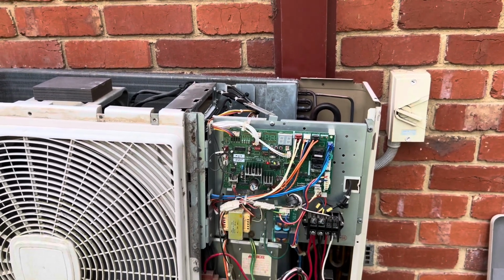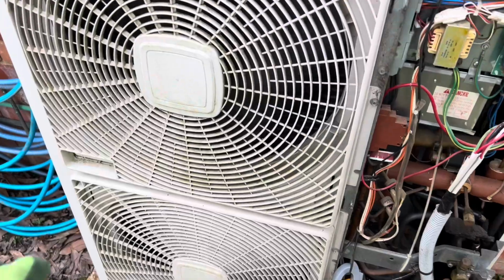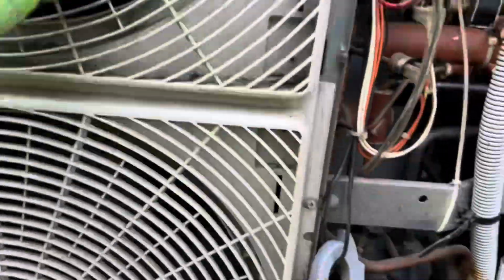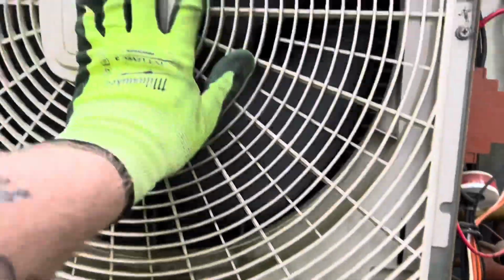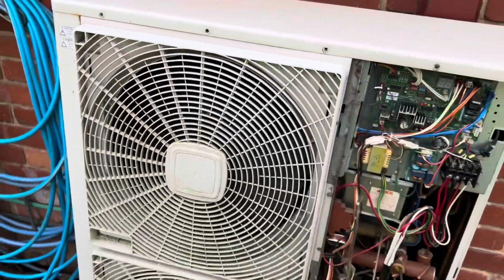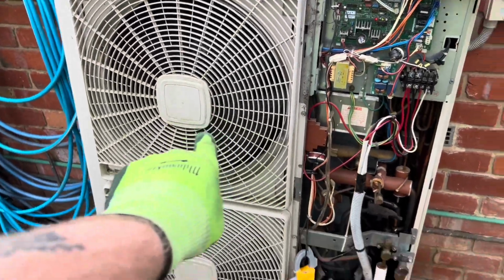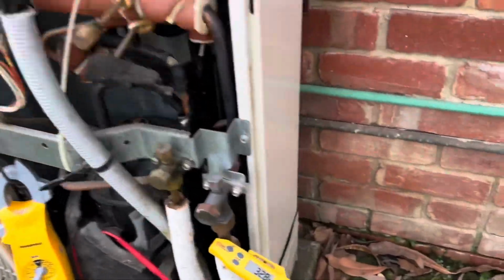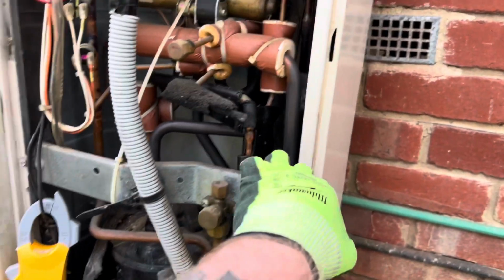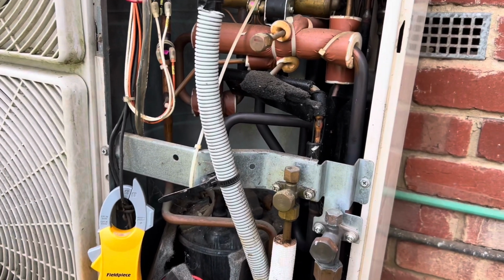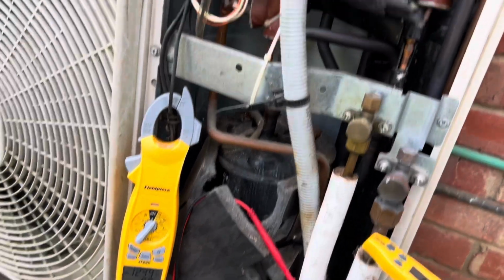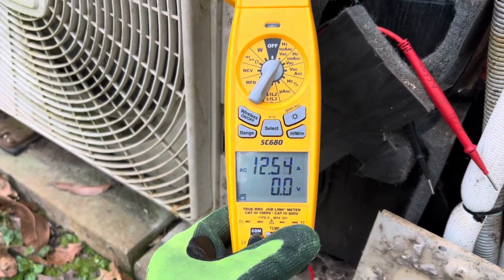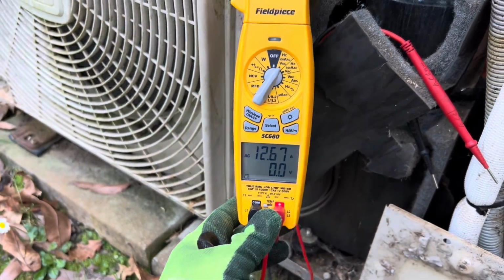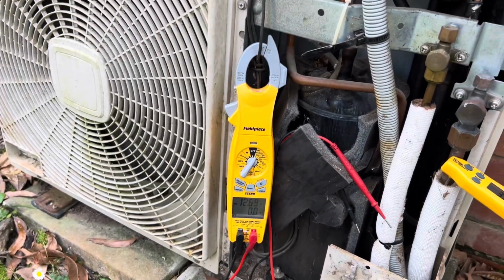It usually faulted out at this point, so this is a good sign - both fans are running. Trying to work out if that one's making a weird bearing noise. I heard a vibration noise before, because this, for whatever reason, had been taken out - I think someone's done some work on this before. Compressor's still running. Let me test the other phases as well. So far, so good.